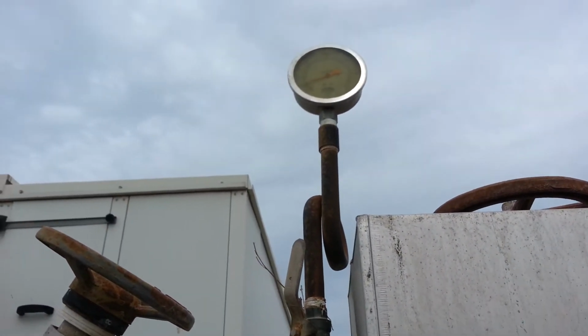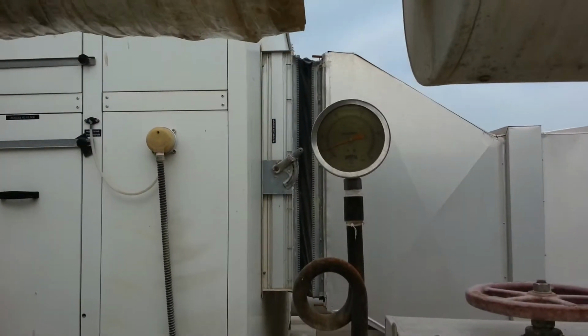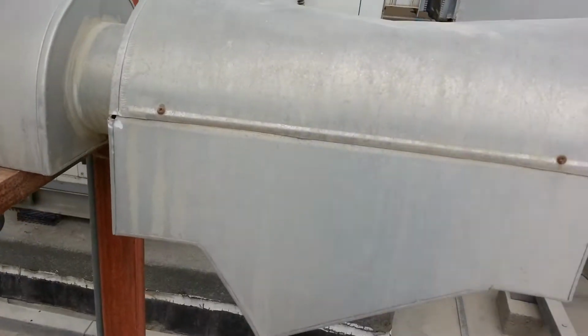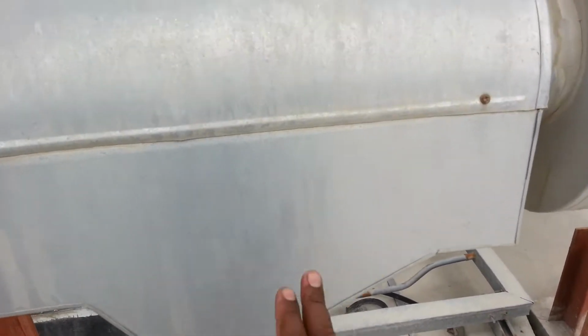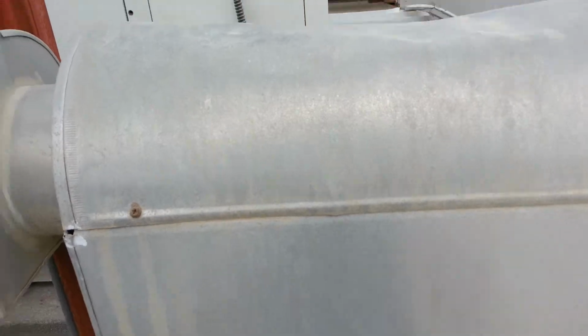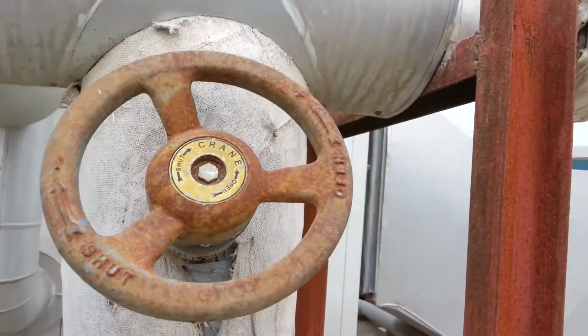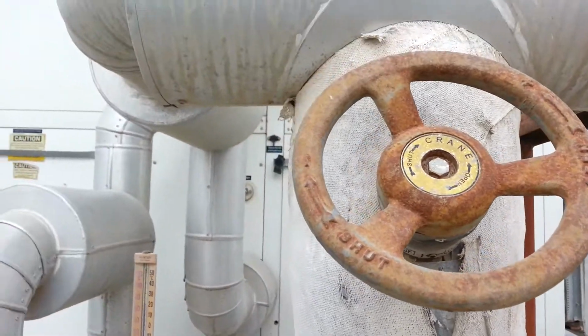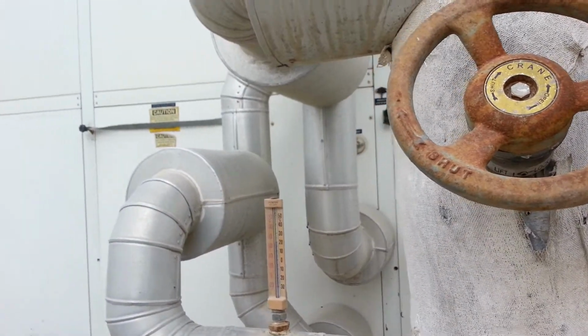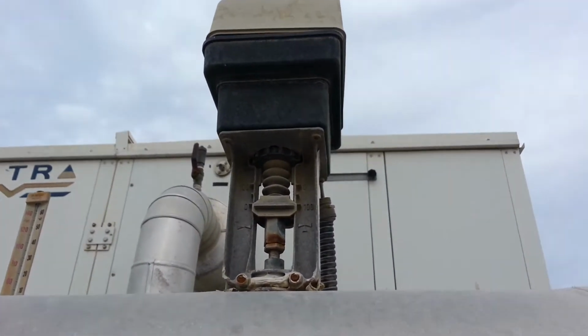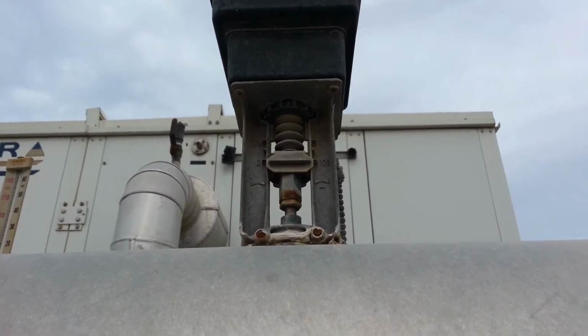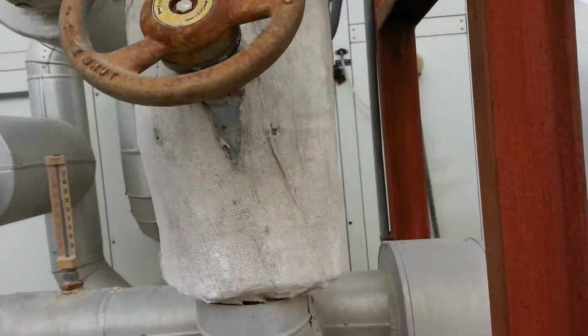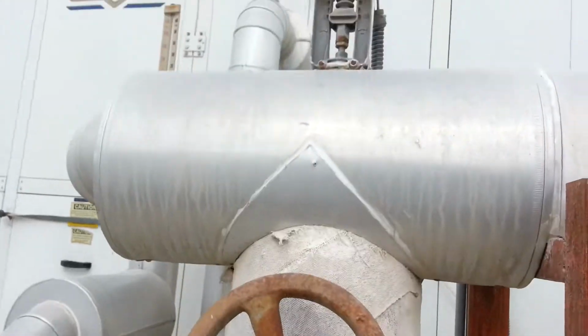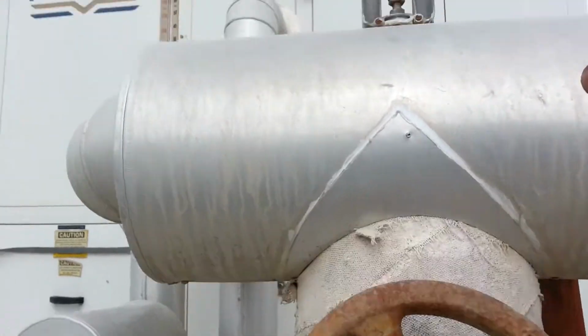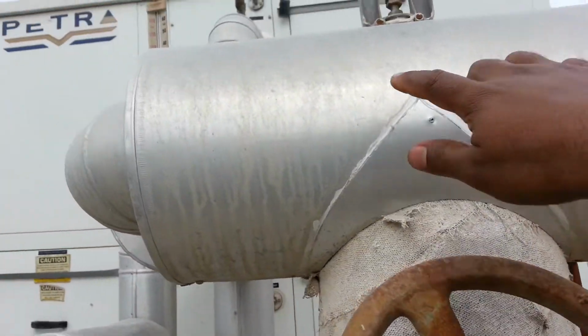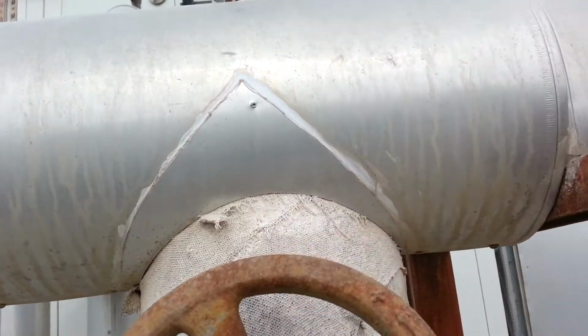Here we can see the water pressure. And here is the filter. This is a chilled water filter. And here there is another balancing valve. This is a bypass line. This is a flow regulation valve, and this is a flow regulation and bypass valve. Here there is a motorized actuator for regulating the water flow. Actually, this is not stopping the water flow. Actually, this is bypassing. You can see the actuator connected in the center of the T bypassing line.